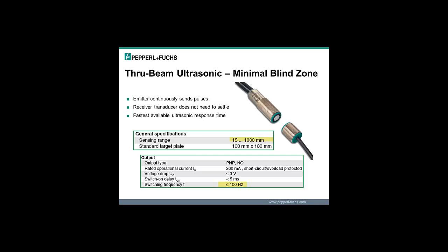You can also see here the switching frequency of an ultrasonic Thru-Beam is 100 hertz for this model. If you were to have the equivalent model for a diffused version, it would probably be around 10 hertz or 15 hertz. So by not having to wait for that emitter transducer to settle and listen, you can go a lot faster. It's a continuous stream of sending and receiving. So the Thru-Beam mode is the fastest available response time for ultrasonic sensors.